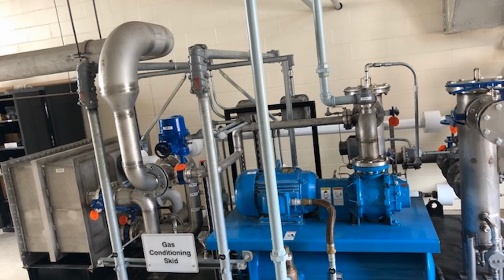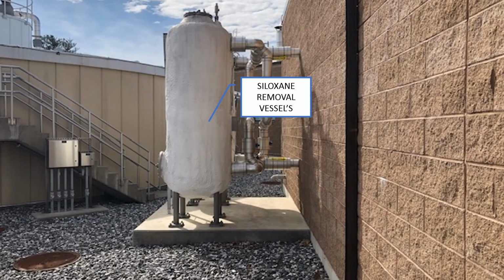The skid has a couple particulate filters. It is taking the gas and dropping it below its dew point through a heat exchanger system, which drops out any remaining moisture. It uses some of that incoming hot gas to heat itself back up, and then it pressurizes itself to 3 to 4 psi, which is the pressure needed to be utilized. Once pressurized, the gas flows outside into 2 activated carbon columns for siloxane removal.